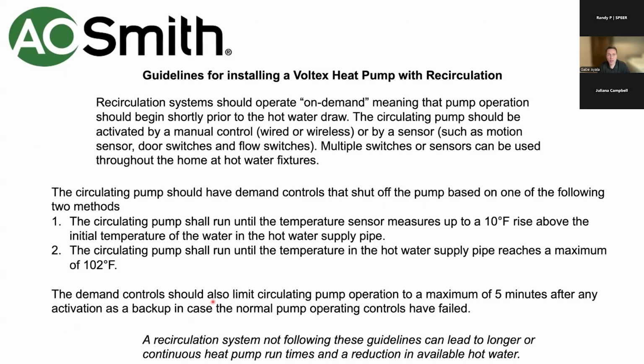Smith. A.O. Smith actually just put out these guidelines for using recirculation with their heat pump water heaters, and they're taking the energy code language and putting it in their O&M manuals, basically saying it's got to turn on using a switch or a sensor and then turn off by sensing either a 10-degree rise or a 102-degree lockout, and then having an automatic timed lockout of 5 minutes. So basically they just took the energy code and put it right in their literature.